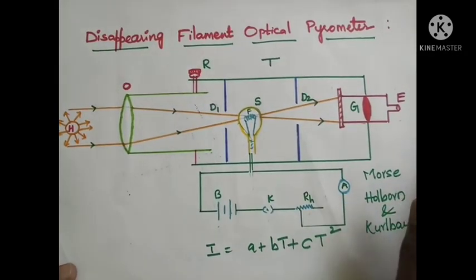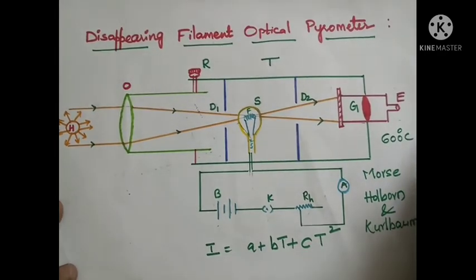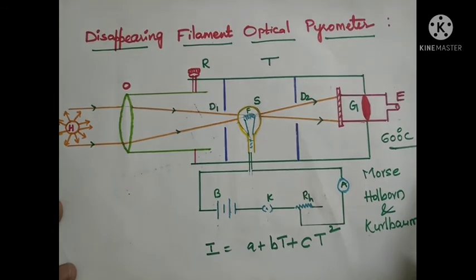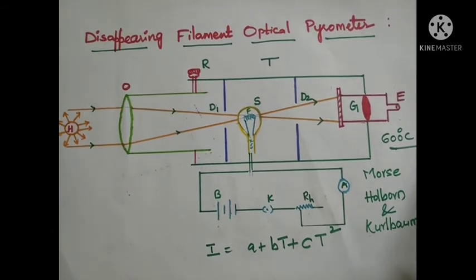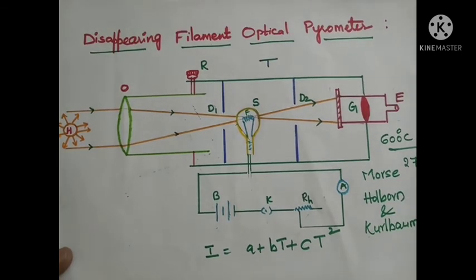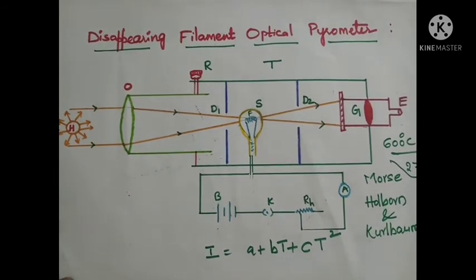With the help of this instrument, we can measure temperatures from 600°C to 1500°C. The range can be raised up to 2700°C by using an additional external device — a rotating sector — which cuts down a known fraction of radiation.